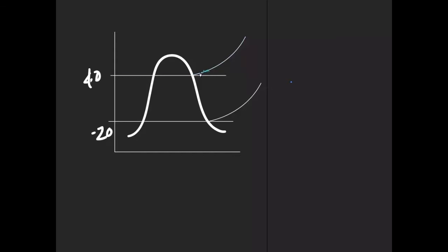So the operation of the machine, we would take suction from down here at the low pressure corresponding to the saturation temperature of minus 20, and if it was an isentropic compressor, you'd get an isentropic line that looks like this. It'd be a vertical line.